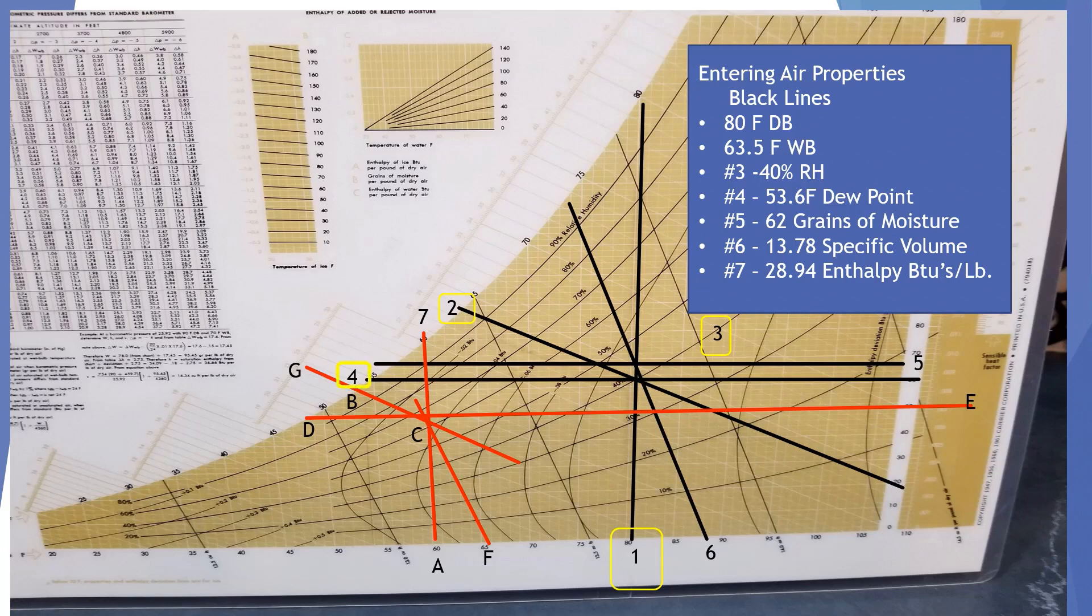At number 4, we have 53.6 degrees of dew point. At 5, we have 62 grains of moisture. At number 6, we have 13.78 specific volume of the air. At number 7, we have 28.94 enthalpy of BTUs per pound of air.